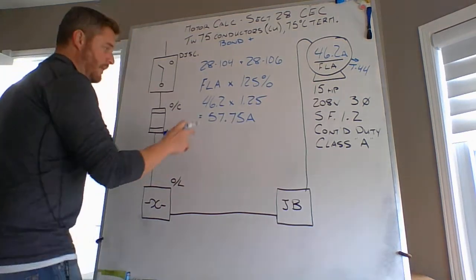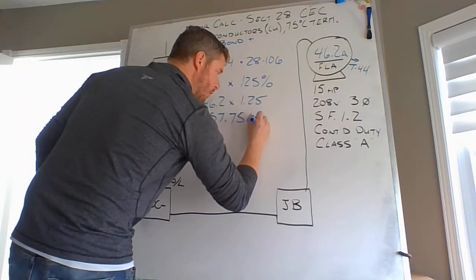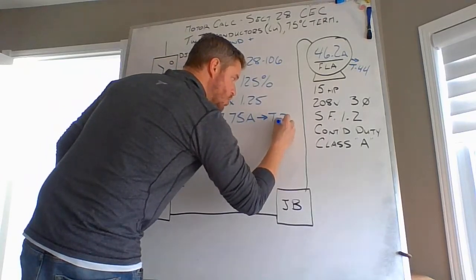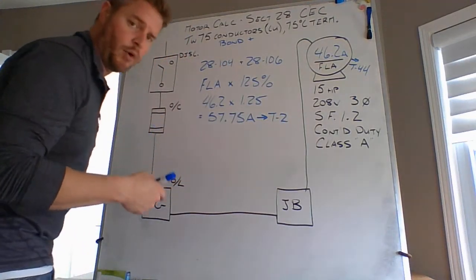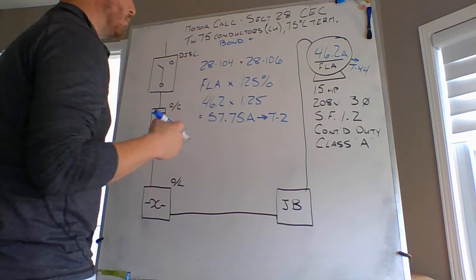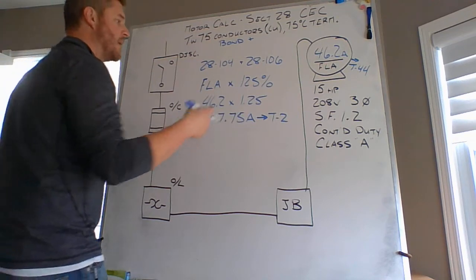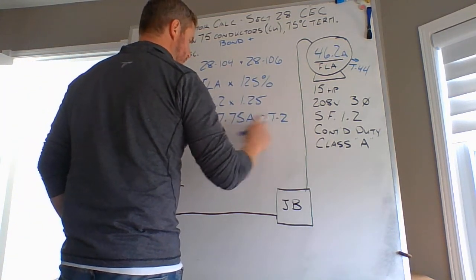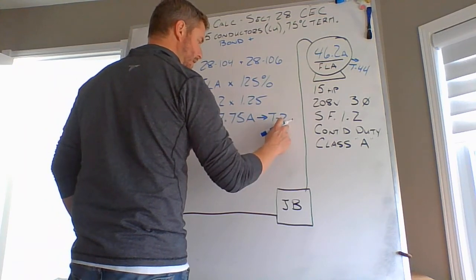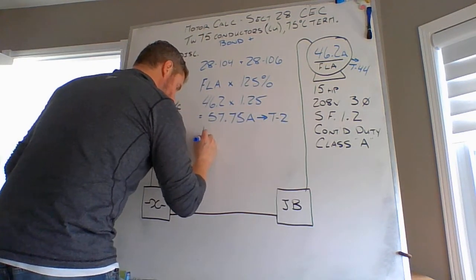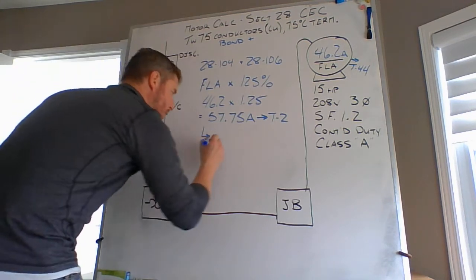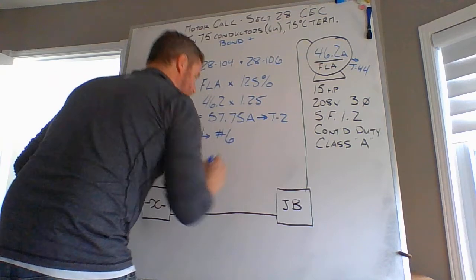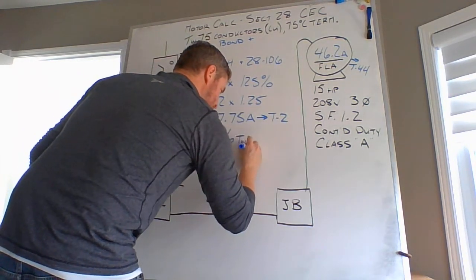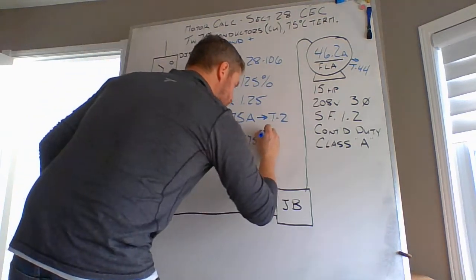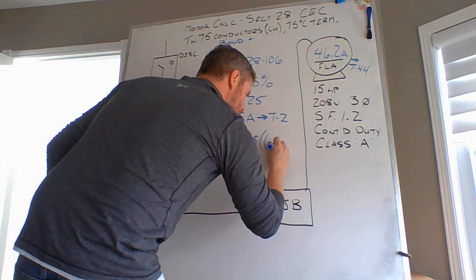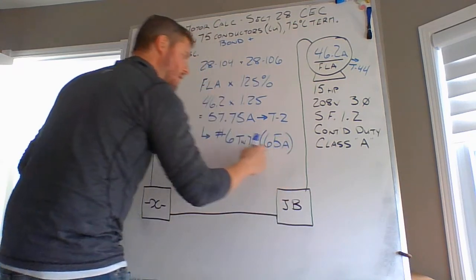I would therefore take my 57.75 amps and go right to Table 2 to figure out which conductor I'm going to supply to suffice this 46.2 amp full load current rating of the motor based on a continuous duty service factor. 57.75 amps, take that to Table 2. Once you take that number to Table 2, you should come up with the fact that you're going to install a number 6 conductor with TW75 insulation rating on it. And it's always a good idea to record its available ampacity in brackets after you have selected a conductor.